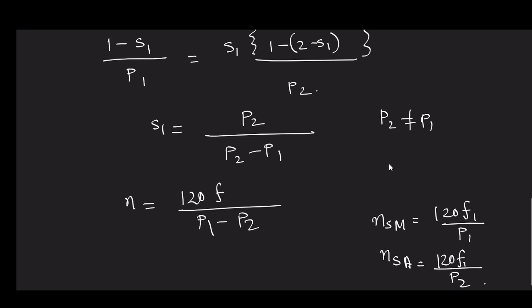In a squirrel cage induction motor, a totally inductive circuit appears to your stator winding, and a totally inductive circuit appears to your supply. That is why it draws a huge amount of magnetizing current to build its MMF, so it can drive the working flux through the air gap. But in case of a doubly fed circuit, you have the slip. So through slip you can inject some power to counterbalance this need, and it may happen that you apply so much power that it doesn't need much capacitive current, the kVAR requirement alters, because you inject kVAR through your slip ring.